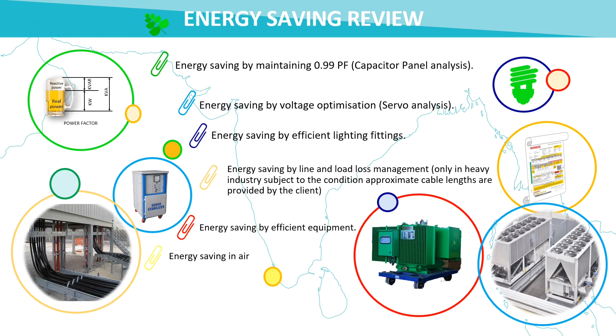In an energy audit, we also provide a safety survey, in which we use thermography to locate hotspots and identify possible faults at points, evaluate earthing pit value and amount of leakage, test the earth leakage system, inspect the electrical system from a safety point of view, and provide recommendations for improvement in fire safety and protection.